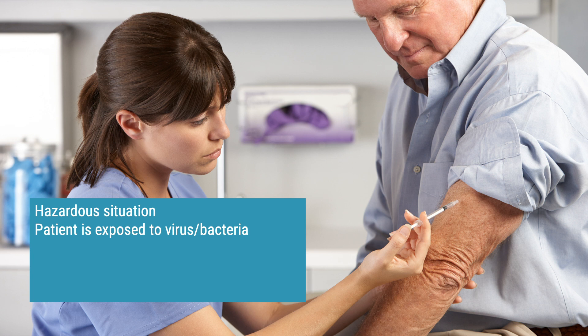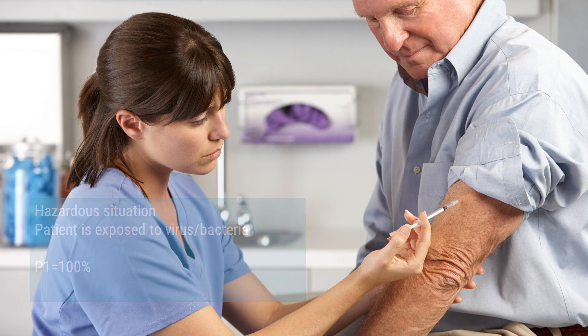Please remember that when we talk about the initial risk estimation, you should think of it as if nothing has been done. Even though we have cleaned the skin and the needle is sterile, there could in theory be bacteria or viruses that you expose the patient to. I would argue that the probability of the hazardous situation occurring is close to 100% — sure, it might not be many viruses or bacteria, but both bacteria and viruses are floating around in mid-air, so the patient is by definition exposed to them. The standard and most manufacturers refer to the probability of occurrence of a hazardous situation as P1. In this case it would be 100%, but it could also be much lower. Even though P1 equals 100%, it doesn't mean you will have an infection every time — I think it's less than once in a thousand needle sticks.